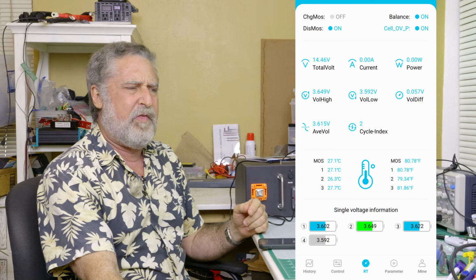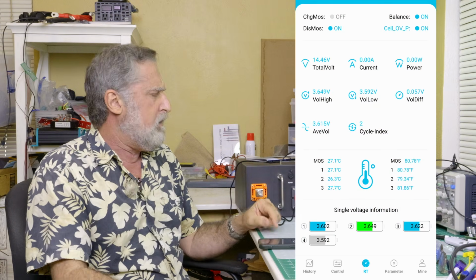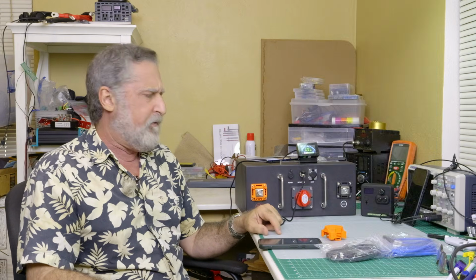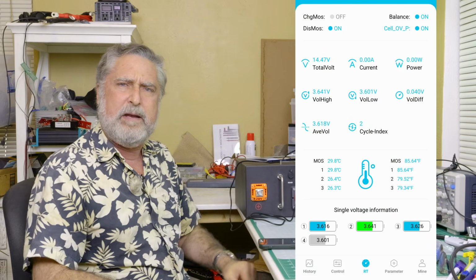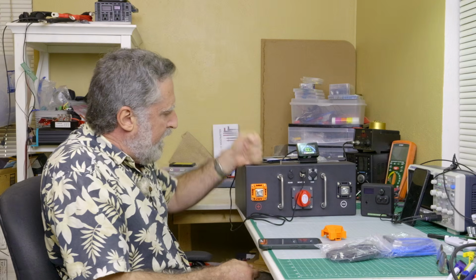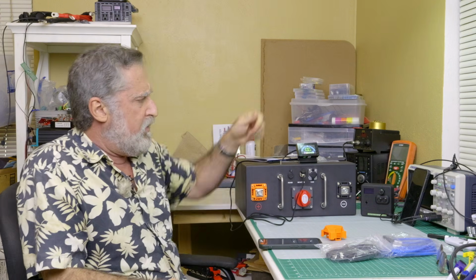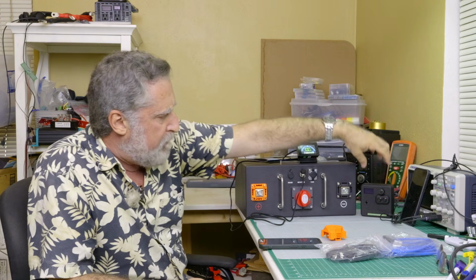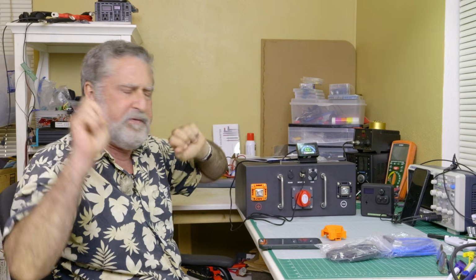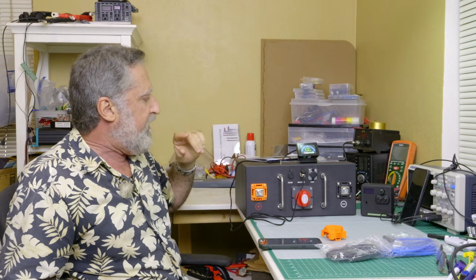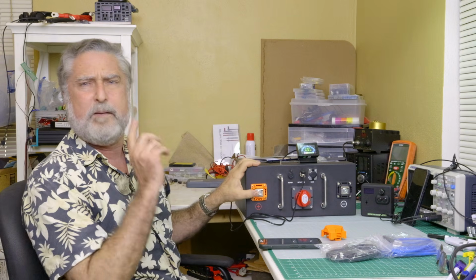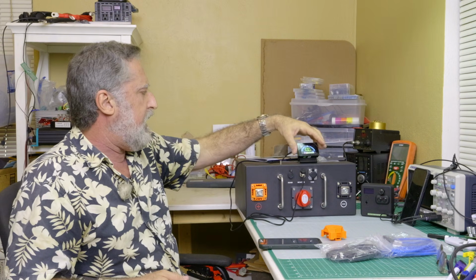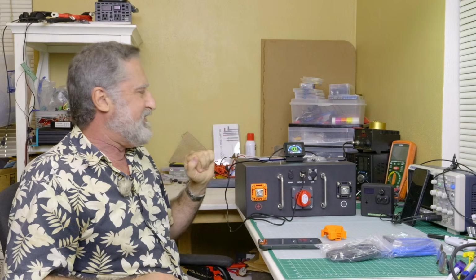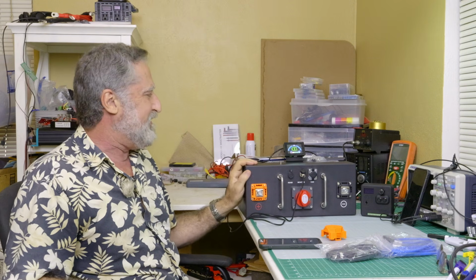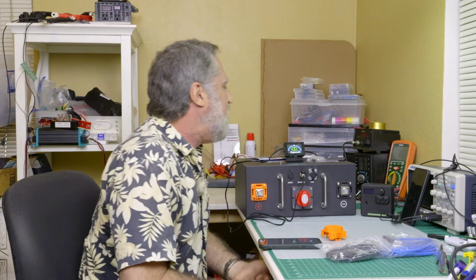Did it, I think, 3 or 4 times total. The last couple of times I didn't come up to high voltage, and it came right into balance. So I took some power out of it, brought it well down, used the bank manager to take it to what the bank manager decides is 100%, as I always do. Then I hooked it up to a calibrated discharge device and let it crank. My device isn't that big, and this is a big battery, so it took 24 hours, and it went down to...